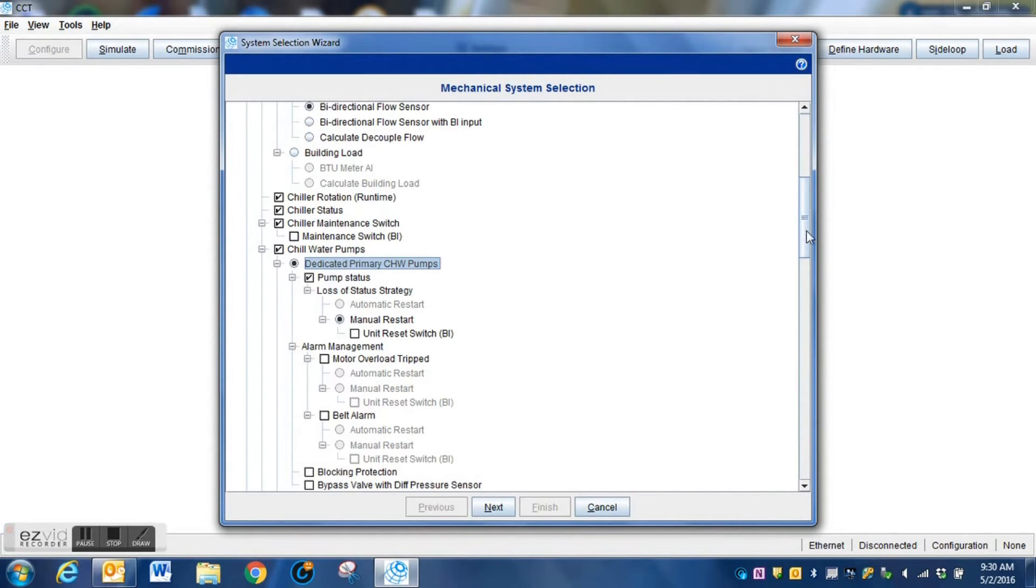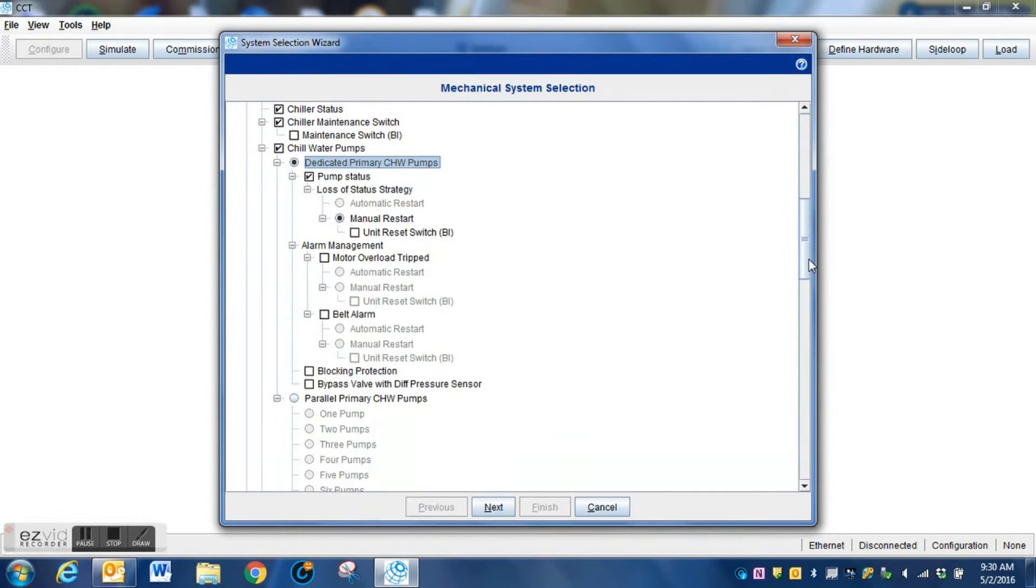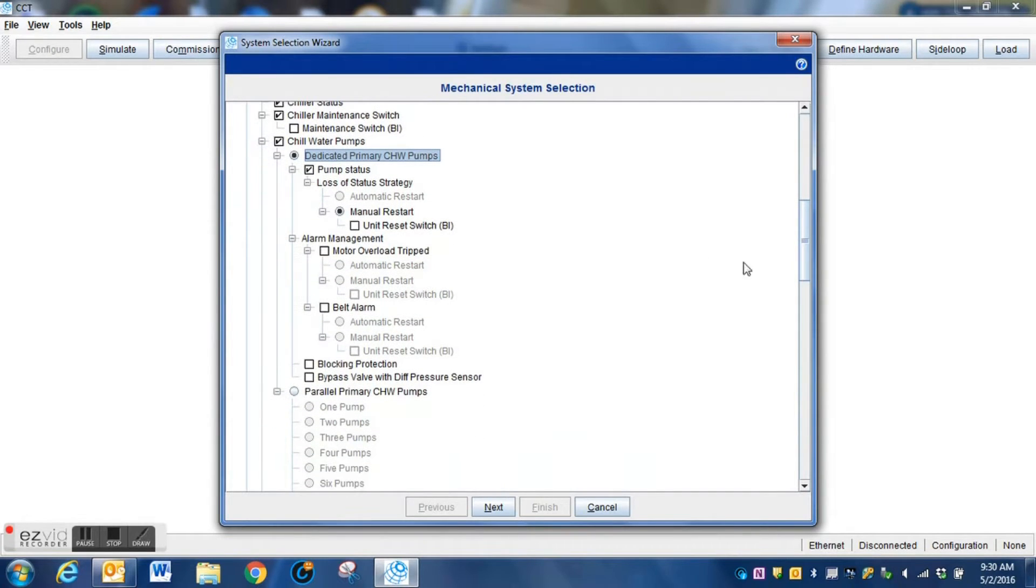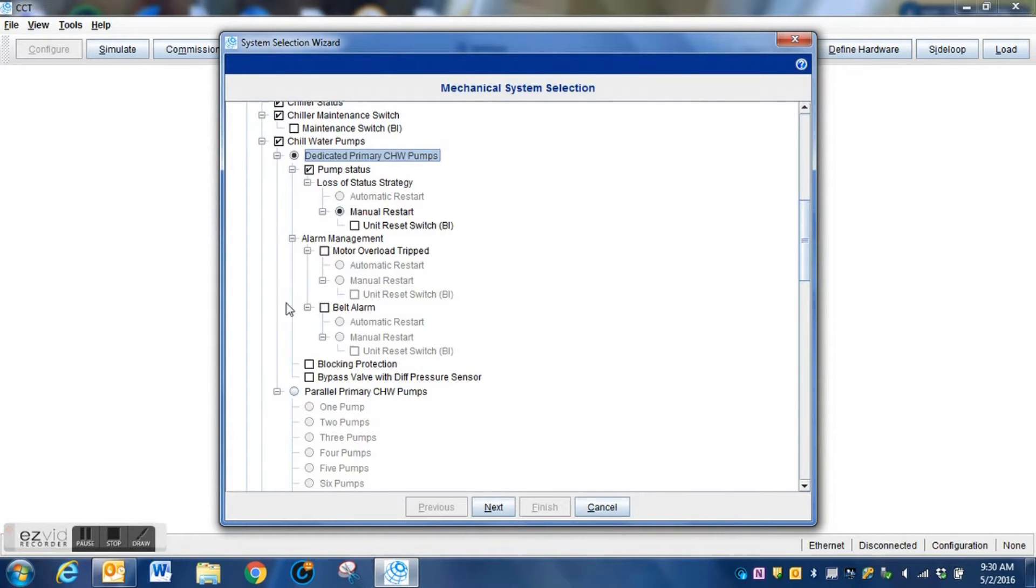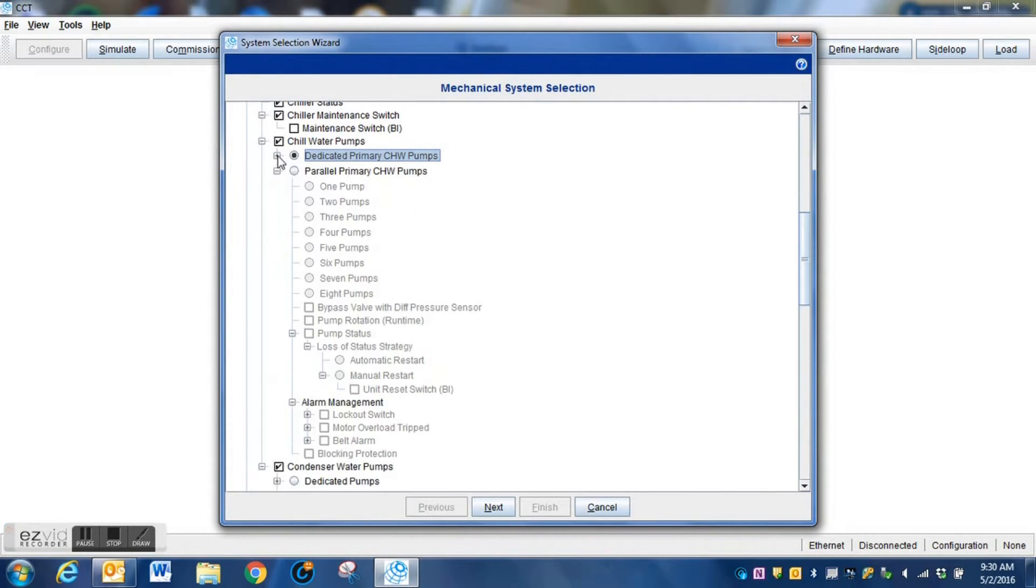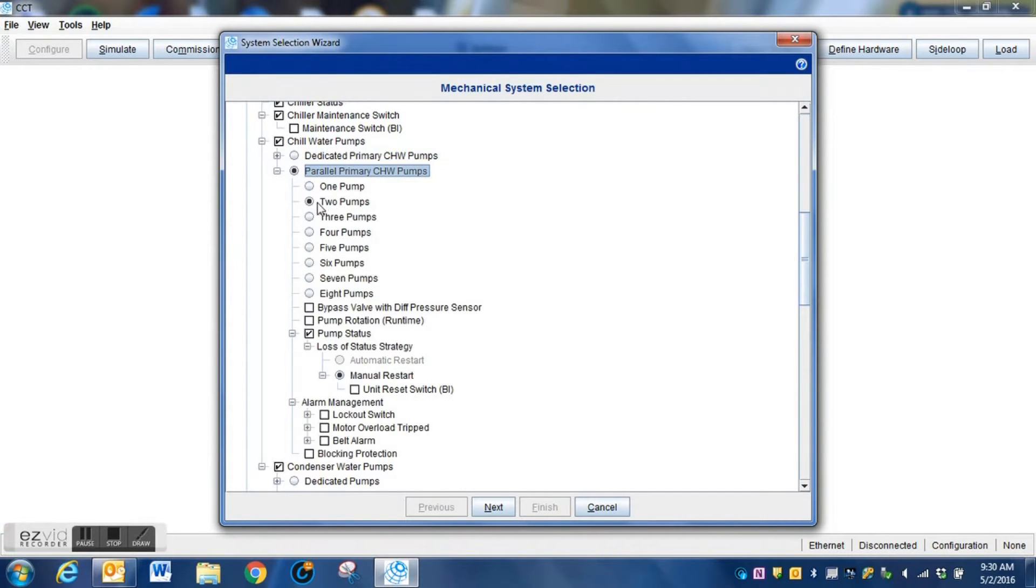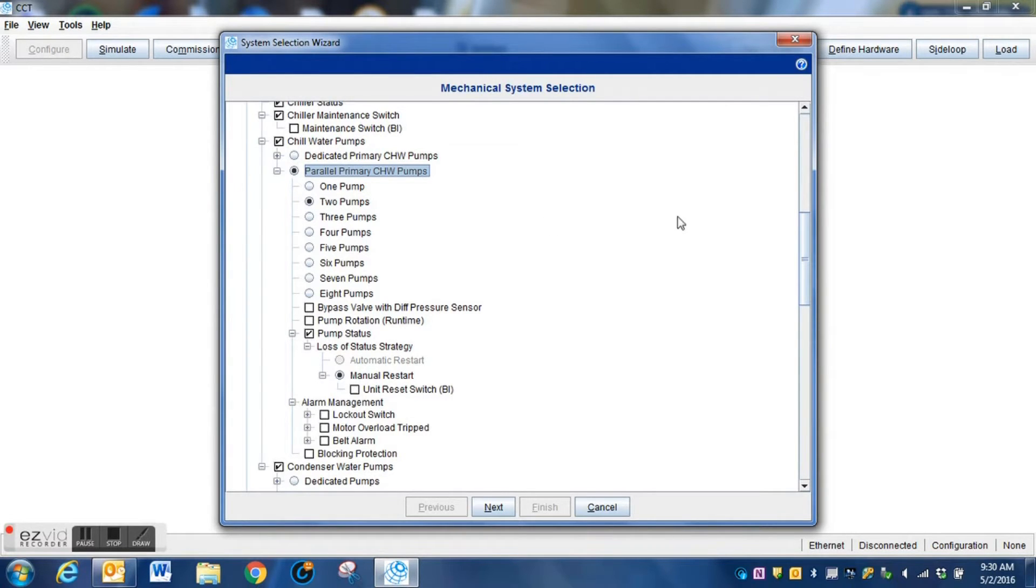You're going to need to know the answers to whether or not there are drives in the system, if the cooling tower is going to have a bypass valve, and that sort of thing. These are just a few examples of some of the information that you will need to know well before you begin writing your program.